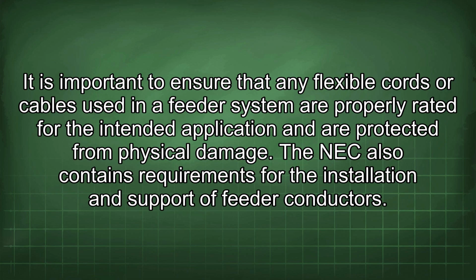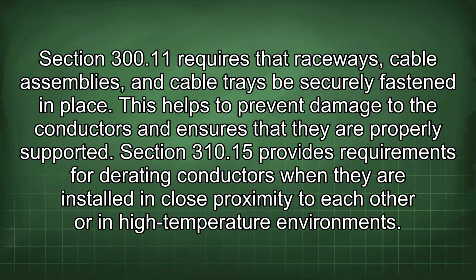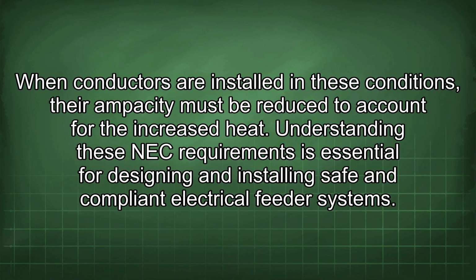The NEC also contains requirements for the installation and support of feeder conductors. Section 300.11 requires that raceways, cable assemblies, and cable trays be securely fastened in place. This helps to prevent damage to the conductors and ensures that they are properly supported. Section 310.15 provides requirements for derating conductors when they are installed in close proximity to each other or in high-temperature environments. When conductors are installed in these conditions, their ampacity must be reduced to account for the increased heat.